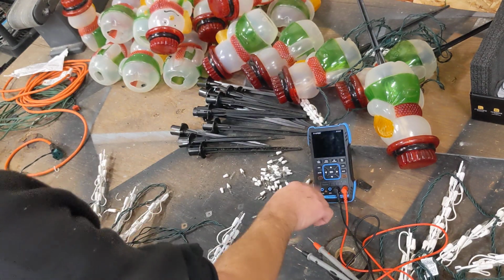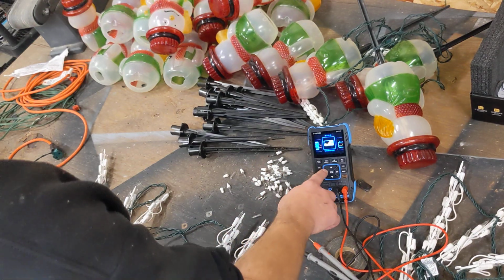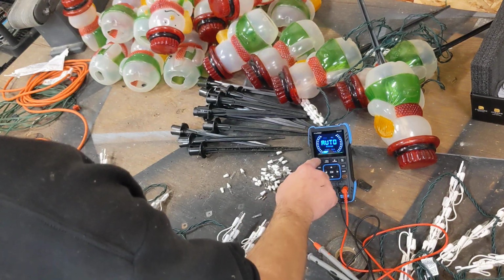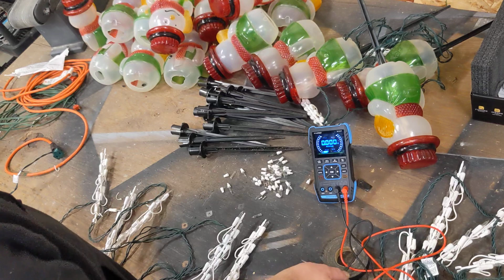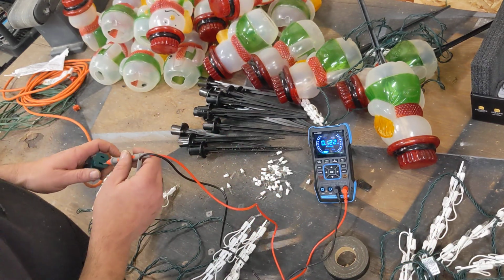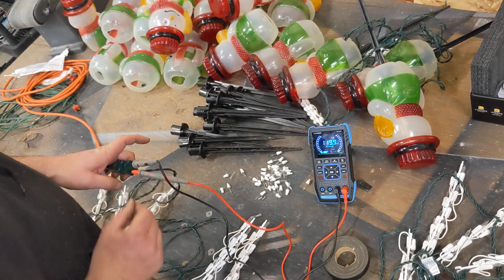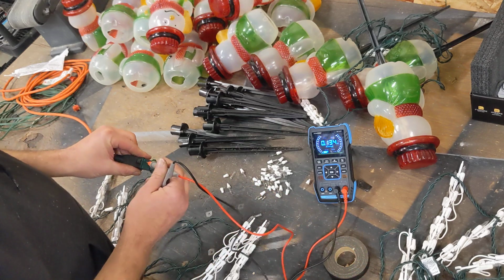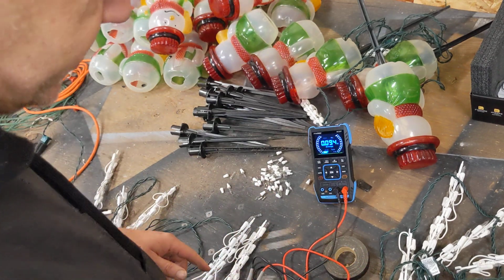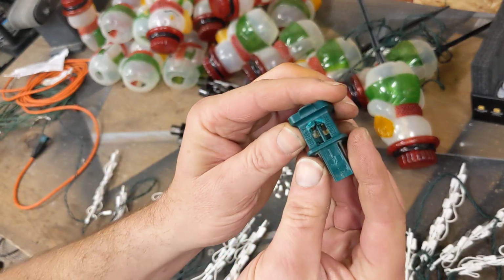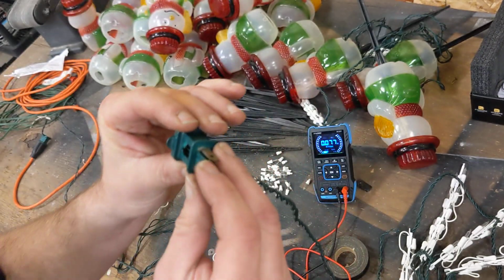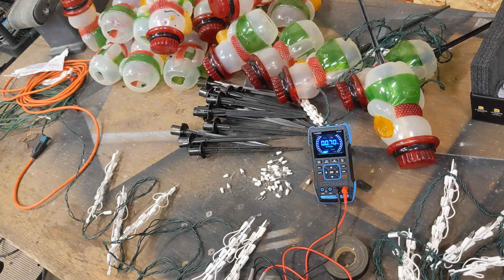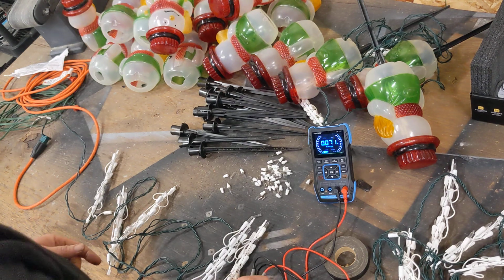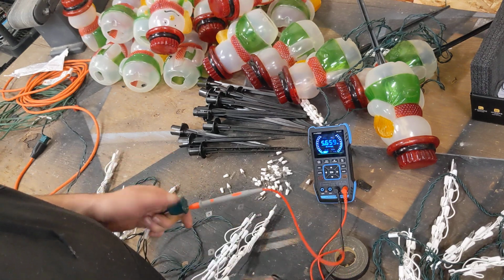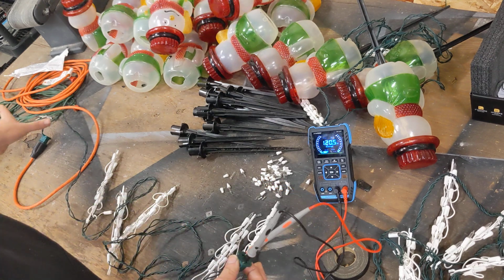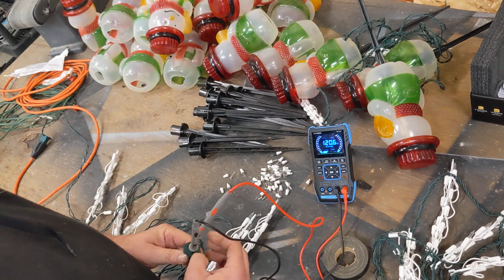So what I'm going to do here is turn on a multimeter. We'll go over to the multimeter function, and I'm going to go into AC volts — these are 120 volts AC. First thing I'm going to do is check power out the back of the plug, and I've got 120 volts, which tells me these 2 fuses inside here are good. The reason I say that is because the person who was messing with them before removed fuses, probably thinking they were the source of the problem. Typically fuses on these do not blow unless you string together more things than you should. So we'll go to the end of the plug, same test, and got 120 volts out, so I know the integrity of my 2 green wires is good all the way through.